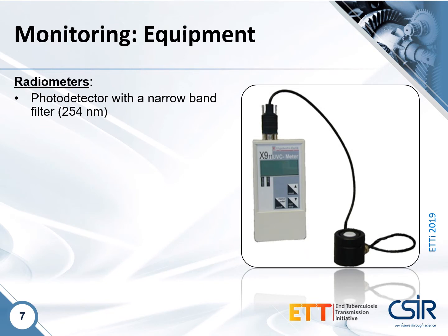In order to do monitoring and measurements of the performance of your upper room UVGI systems, you need a radiometer. A radiometer is essentially a photodetector with a narrow band filter for UVC, that is in the range of 254 nanometers. It is important to filter out UVA and UVB so that you are only measuring the UV in the 254 range, so that your measurements are not affected by sunlight specifically.